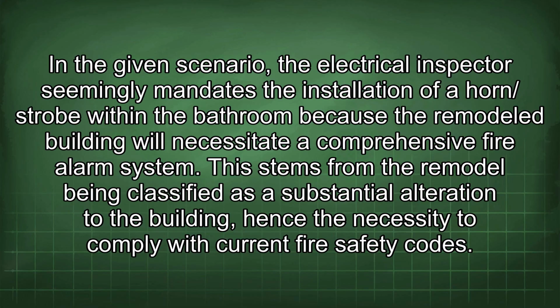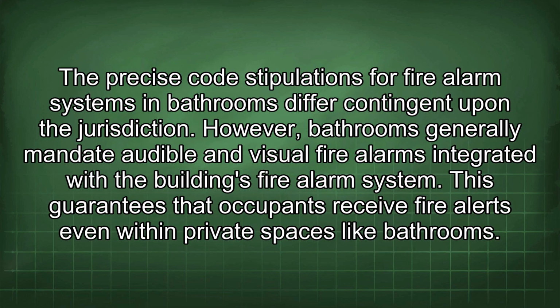This stems from the remodel being classified as a substantial alteration to the building, hence the necessity to comply with current fire safety codes. The precise code stipulations for fire alarm systems in bathrooms differ contingent upon the jurisdiction. However, bathrooms generally mandate audible and visual fire alarms integrated with the building's fire alarm system. This guarantees that occupants receive fire alerts even within private spaces like bathrooms.